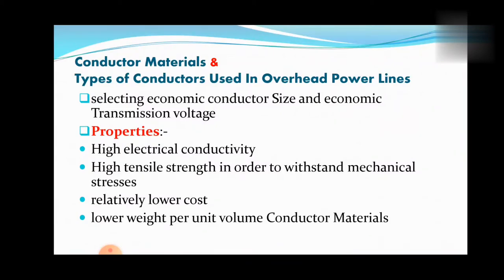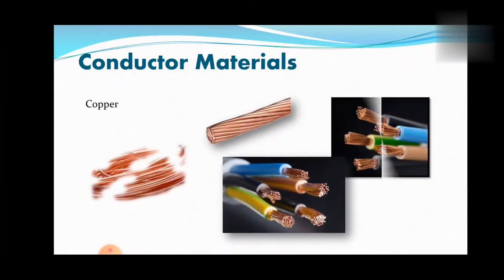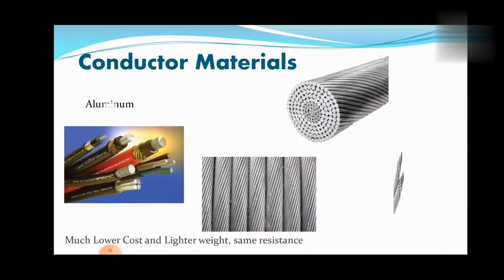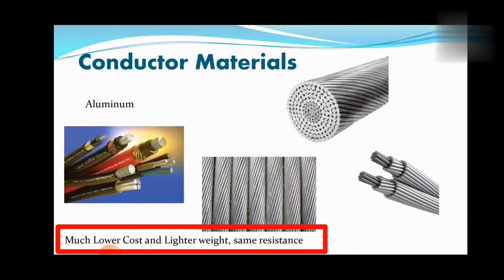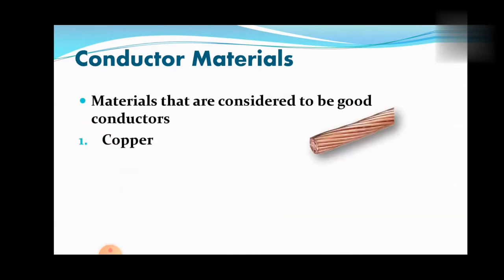Copper was the preferred material for overhead conductors in earlier days, but aluminum has replaced copper because of the much lower cost and lighter weight of the aluminum conductor compared with a copper conductor of the same resistance. Next, I am explaining some materials that are considered to be good conductors: copper, aluminum, cadmium copper, and other materials.